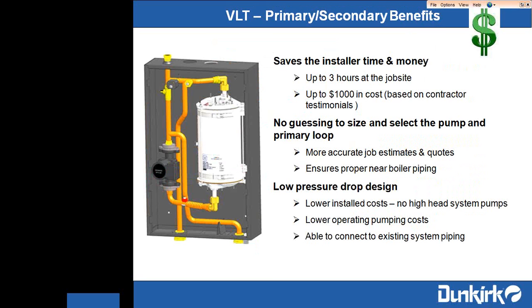The way the Helix is designed, they can literally take out that old boiler, cut it out, put in a Helix, and then hook up their supply and return tubing to the boiler without having to engineer a primary secondary loop. And the reason is we have that primary secondary loop pre-installed within the jacket of the boiler. So again, that saves the contractor probably a half a day in having to design and build the primary secondary loop, and about $1,000 between his labor and materials.